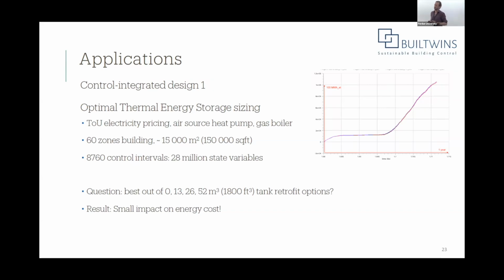We thought something must be wrong, so we dug into the results. It turns out that because the thermal mass of the building envelope is so much more than the tanks—we're talking 50 cubic meters for the tank, but the equivalent tank size of the building envelope is 200 times more—the tank size is still negligible, since MPC could already store energy in the building envelope. It could do it slightly more efficiently with less heat losses in a tank, but it didn't make all that much difference.